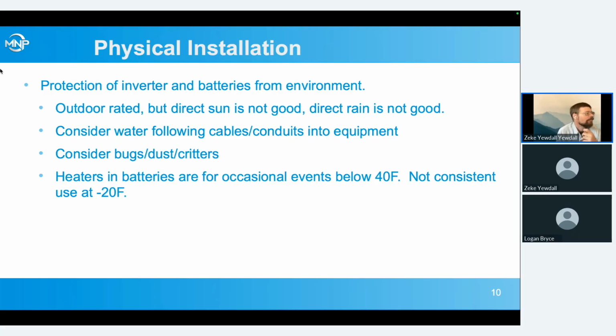The logic behind the heater is it only turns on if the batteries are trying to charge and they are at low temperature. So at nighttime, it's not going to turn on. And this can be a problem because, I mean, it's got the benefit that it doesn't drain your batteries overnight just trying to keep the batteries warm. But when the sun comes out the next day and it starts to charge, instead of charging, it's just going to put 300 watts into the heater in each battery until it gets that battery back up to temperature to charge.